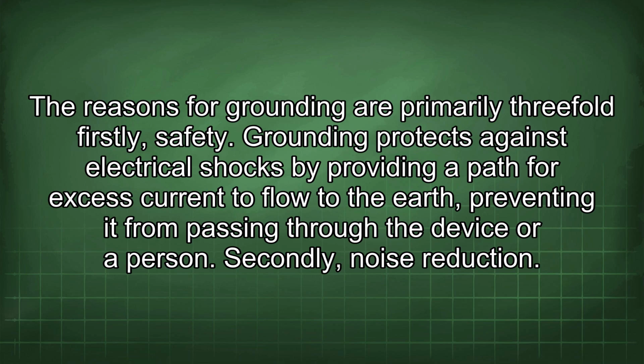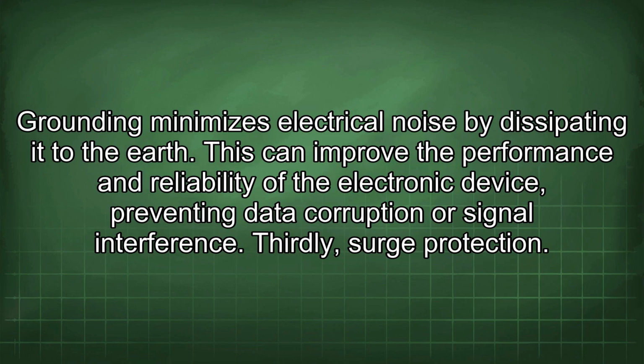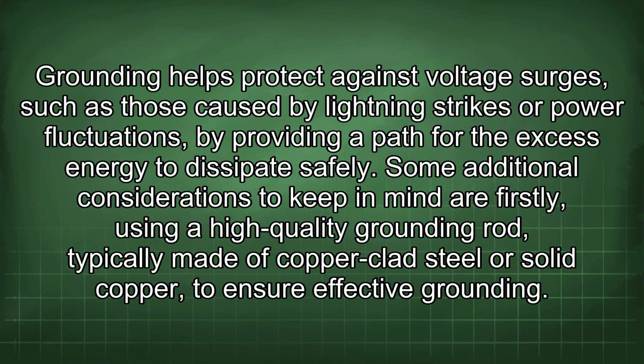Secondly, noise reduction. Grounding minimizes electrical noise by dissipating it to the earth. This can improve the performance and reliability of the electronic device, preventing data corruption or signal interference. Thirdly, surge protection. Grounding helps protect against voltage surges, such as those caused by lightning strikes or power fluctuations, by providing a path for the excess energy to dissipate safely.